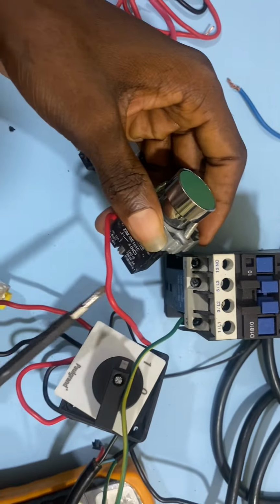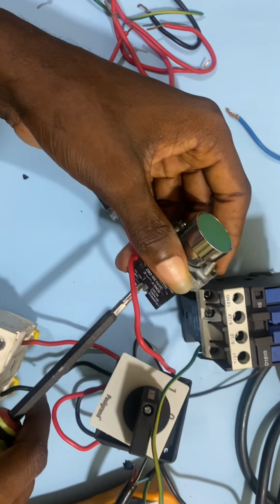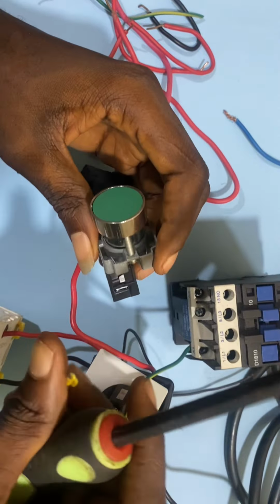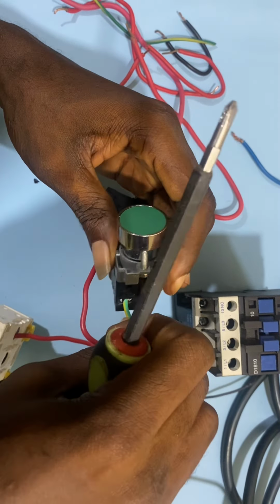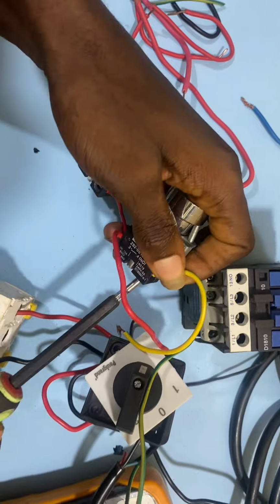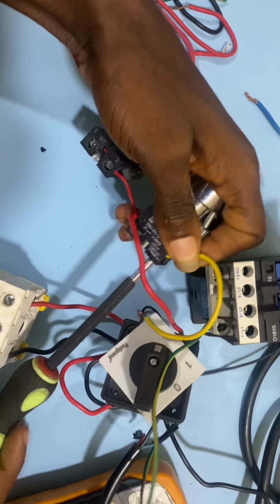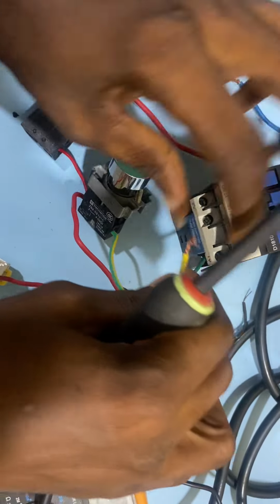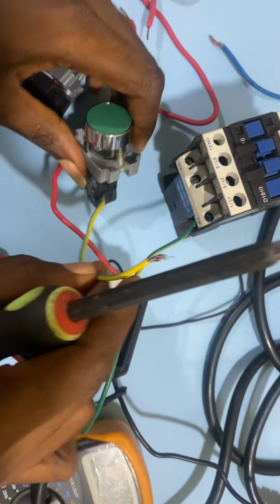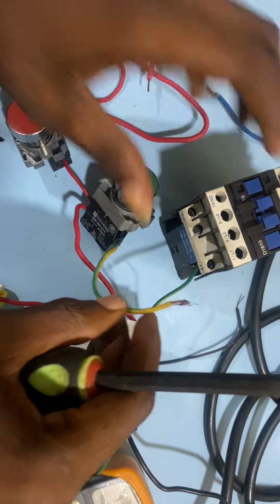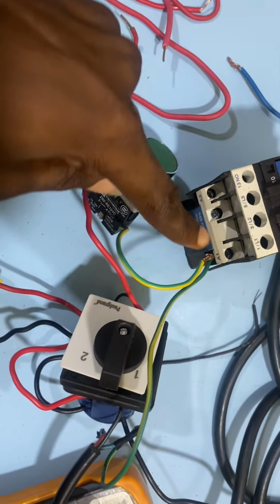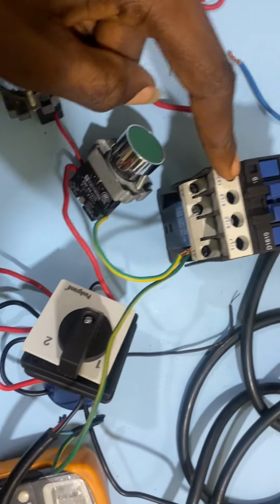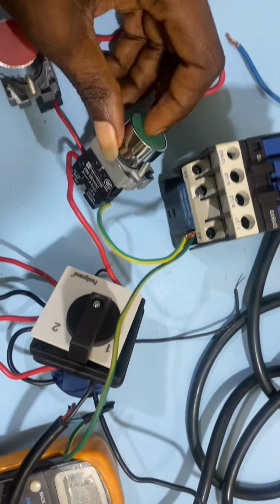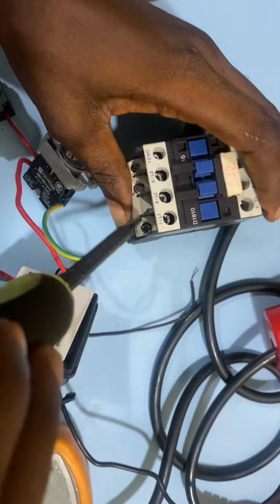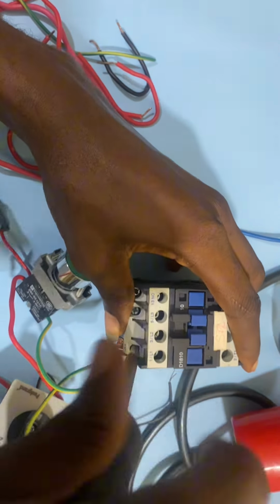So you see terminal 4 of my start button to the contactor. So this is my terminal 4 of the start button. All right, I'm done with that. So I'm going to connect it to my coil contact of the contactor, because it's a live wire that is coming from there. So I'm going to connect it here, and after connecting it to the coil contact of the contactor, I will loop it to the normally open contact to create a holding contact for the start and stop button. So I'm connecting it at this point again. So I'm going to flag it back.